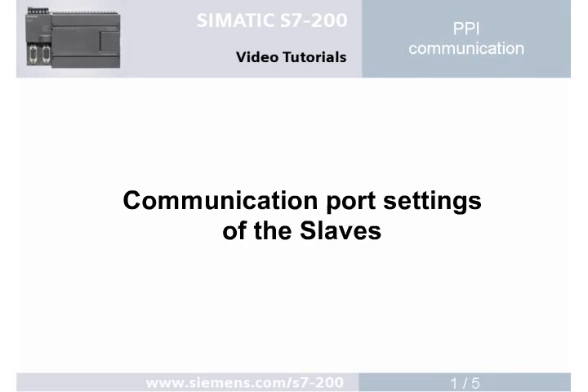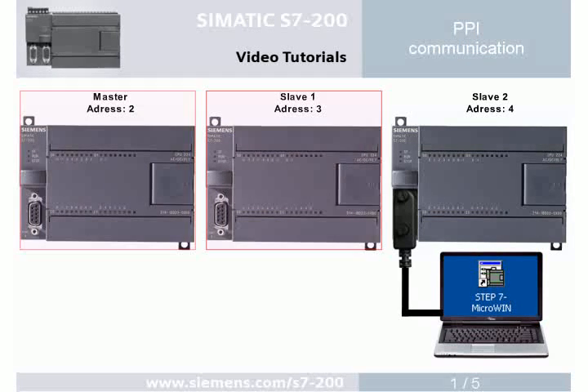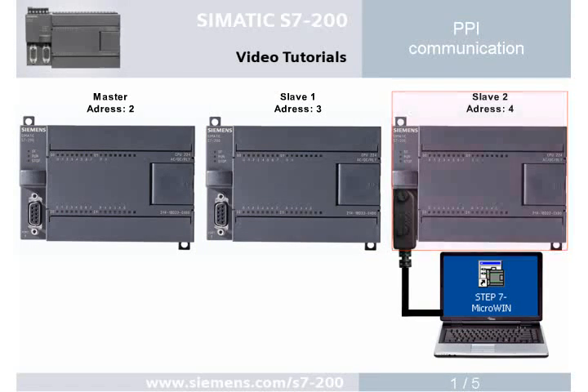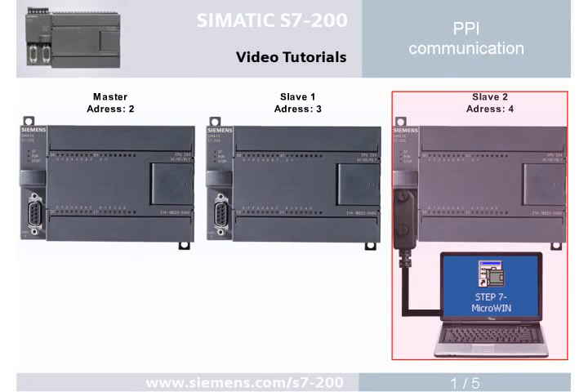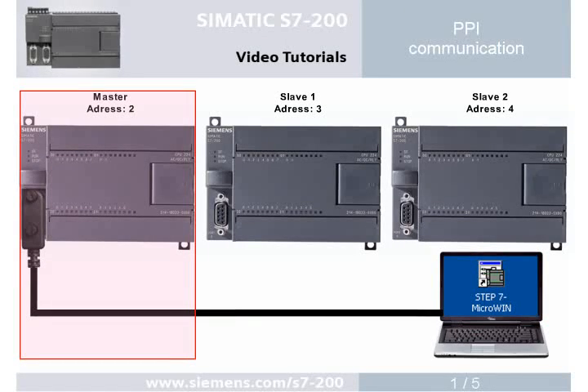Step 1: Communication port settings. For identification, unique addresses must first be assigned for the PLCs. The master receives address 2, slave 1 the address 3, and slave 2 the address 4. Address assignment is illustrated with slave 2 as an example. To avoid overlapping addresses, only the PLC to be configured must be connected with the programming device.